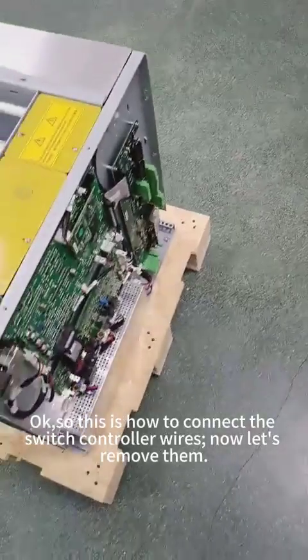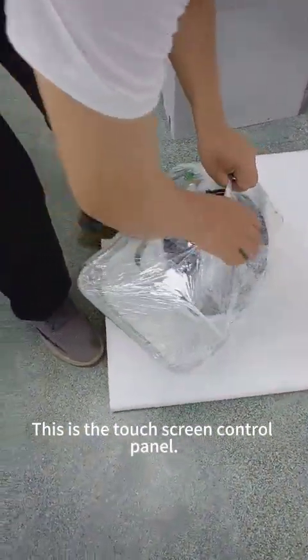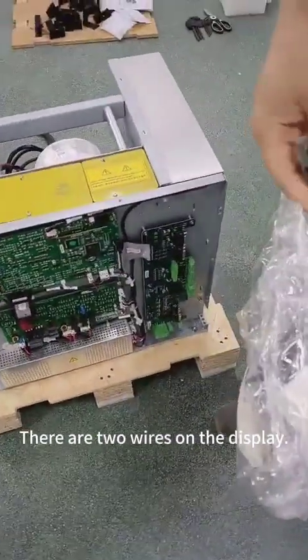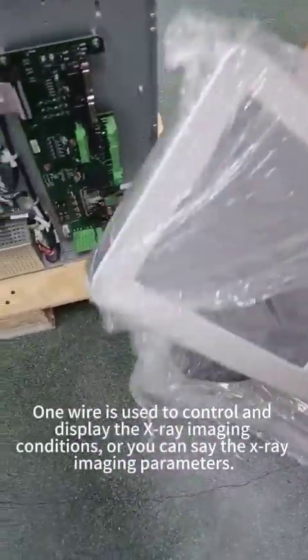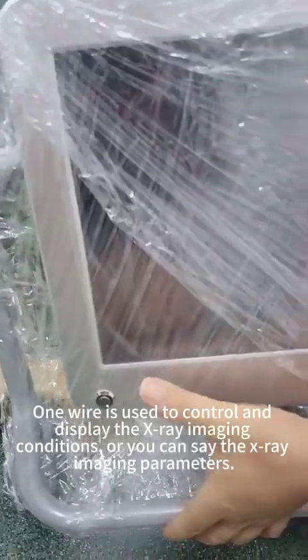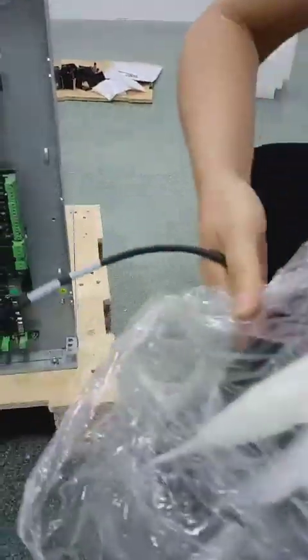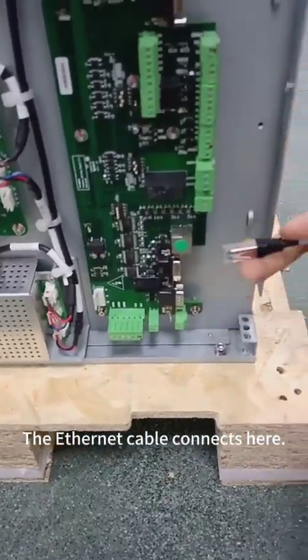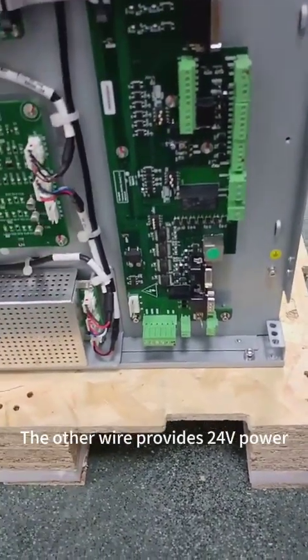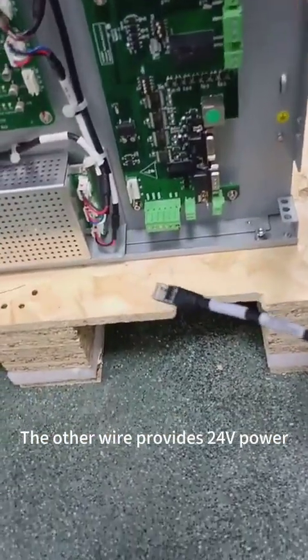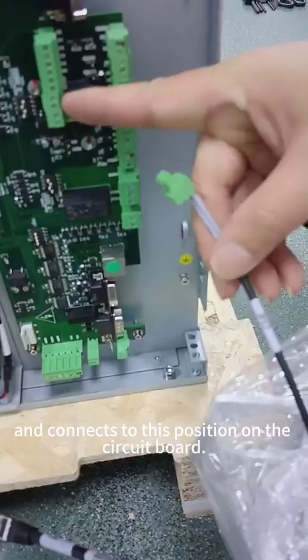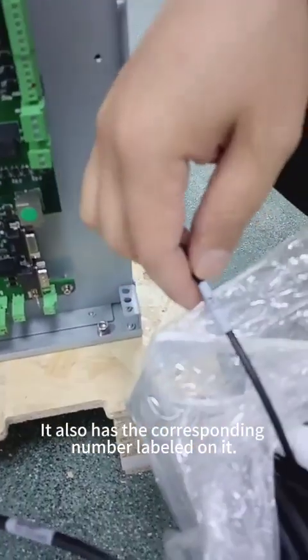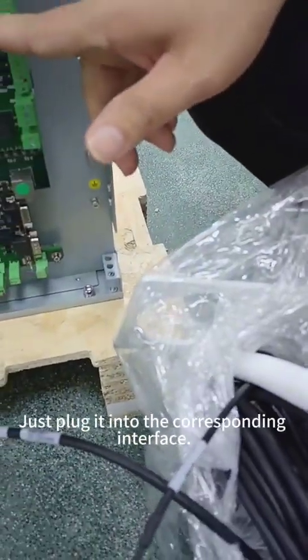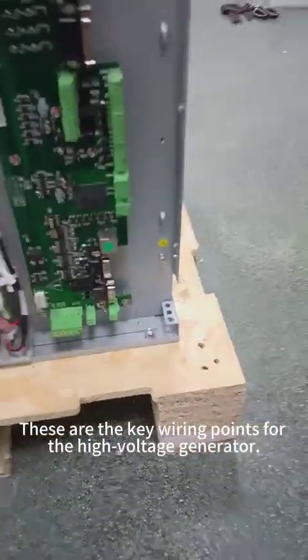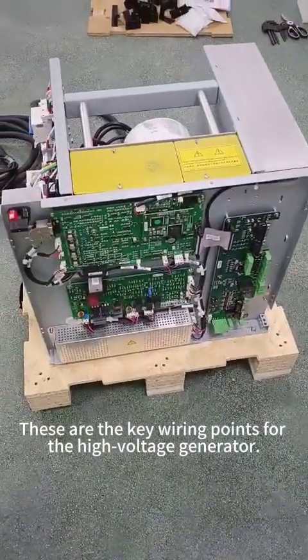Now, let's remove them. This is the touchscreen control panel. There are two wires on the display. One wire is used to control and display the X-ray imaging conditions, or you can say the X-ray imaging parameters. The Ethernet cable connects here. The other wire provides 24-volt power and connects to this position on the circuit board. It also has the corresponding number labeled on it. Just plug it into the corresponding interface. These are the key wiring points for the high voltage generator.